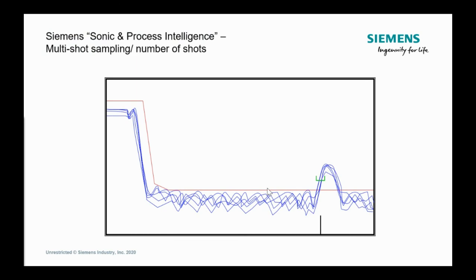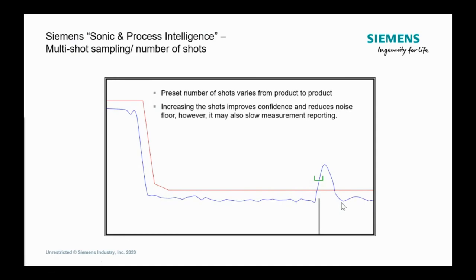Okay, and it's going to apply something called a Kalman filter or a Kalman algorithm. For the math geeks in the room, that is a mathematically recursive algorithm that looks at the most recent echo, and then it'll give a little bit less weighting to the next most recent, and a little bit less weighting to the next most recent, and so on. And what that does is noise by its very nature is random, as you see here across the noise floor. But the one thing that's pretty consistent among all of these different echoes is the actual echo itself. So what it's going to do is take those and apply this Kalman algorithm, or a Kalman filter, if you will, and basically try and optimize that performance based on a number of different measurements in order to get you the cleanest signal that it can.